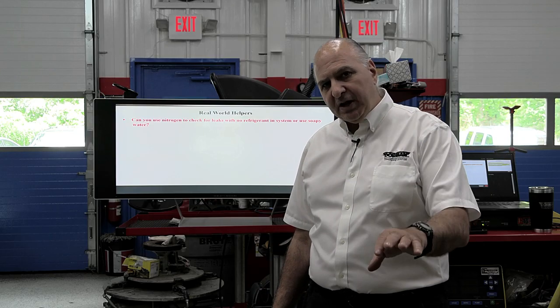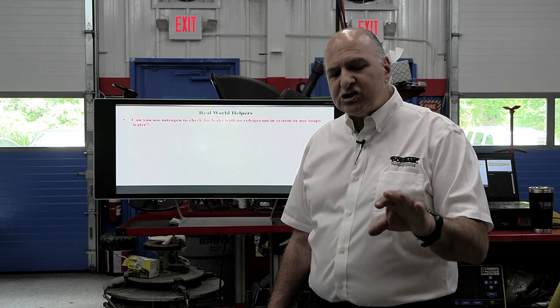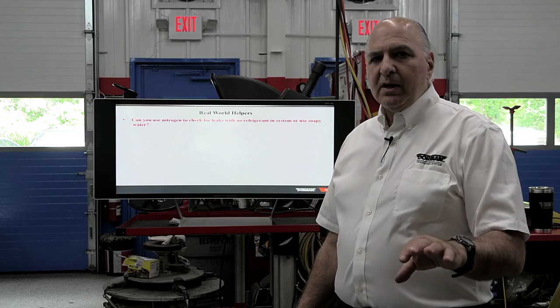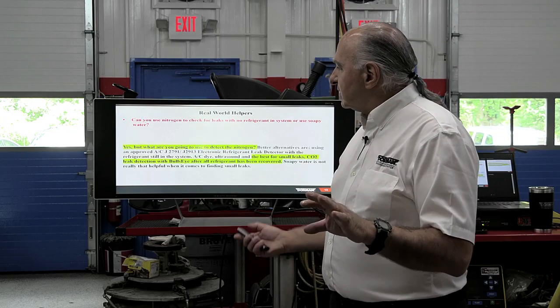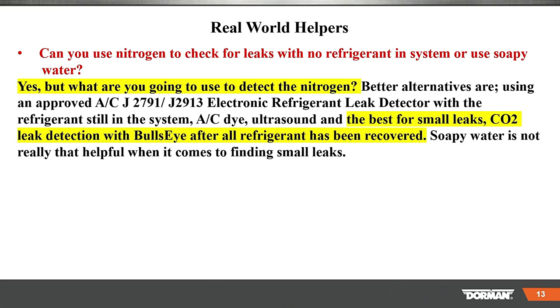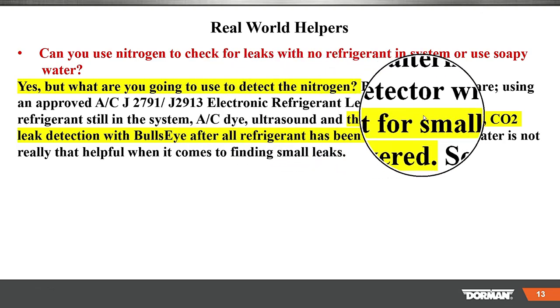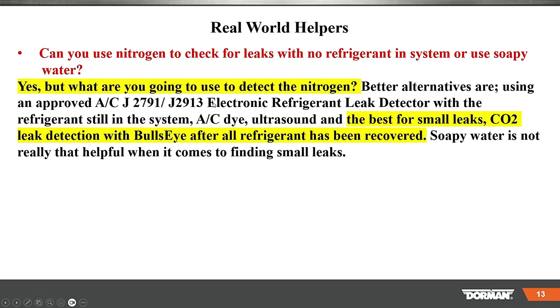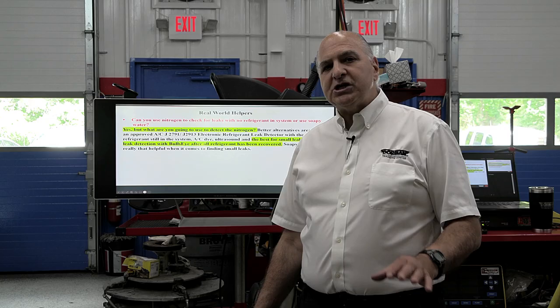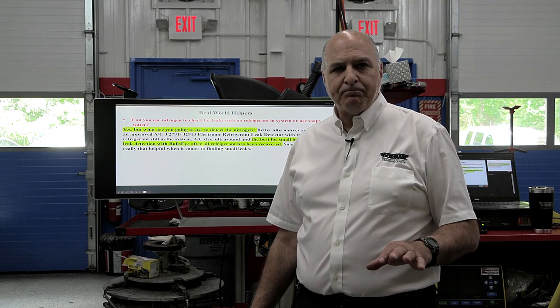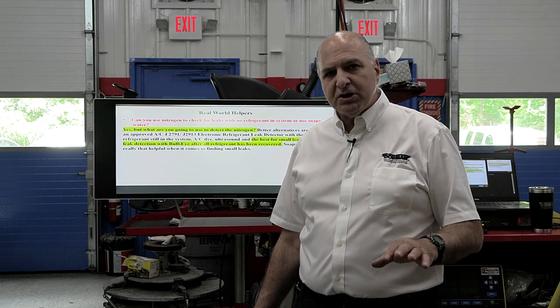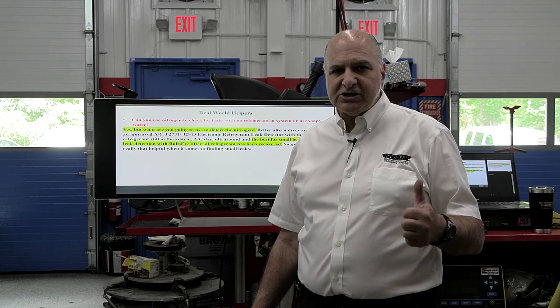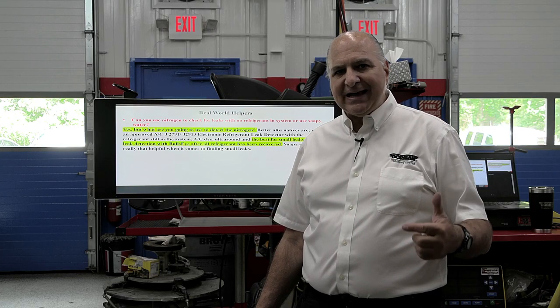You got to put it under pressure, okay? You're going to see a little video coming up where we use CO2, okay? Here it says nitrogen, but you don't have a nitrogen detector. You do need an approved J2913 electronic refrigerant leak detector that we're going to talk about in a minute. We use CO2 along with Bullseye. Okay, not a sales pitch. CO2 you can use with your gas analyzer or the Bullseye kit.